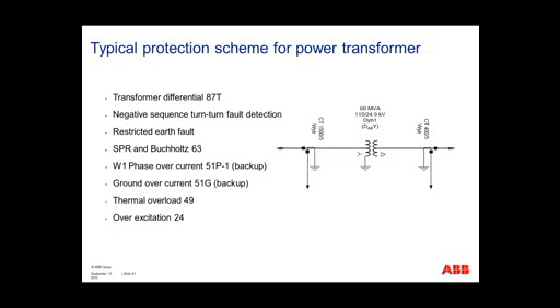So, to review what we've been over, for a typical protection scheme for power transformers, we have our transformer differential protection, which is our number one protection. We have our negative sequence turn-to-turn differential fault protection. We have our restricted earth fault protection for faults close into the neutral of the transformer. We have our sudden pressure relay, our Buchholz relay. We have our overcurrent protection on the high side, and our ground overcurrent protection is backup. We've talked about thermal overload protection and our overexcitation protection.